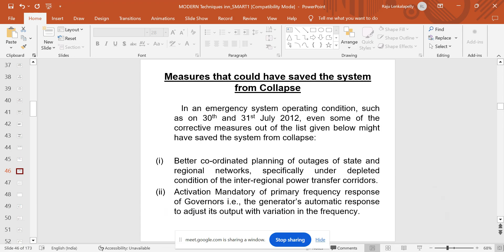We have the frequency system where under-frequency based load shedding is the reliable trip. But apart from under-frequency measurement, we should also have df/dt based load shedding, as the committee suggested. Then how will you get the rate of change of frequency? What is the advantage to the operator? Frequency is reducing, but how fast my frequency is reducing requires some other equipment. Therefore, to measure frequency, voltage, and current with respect to time, and rate of change of frequency, they suggested some PMU, phasor measurement unit, or synchrophasors.